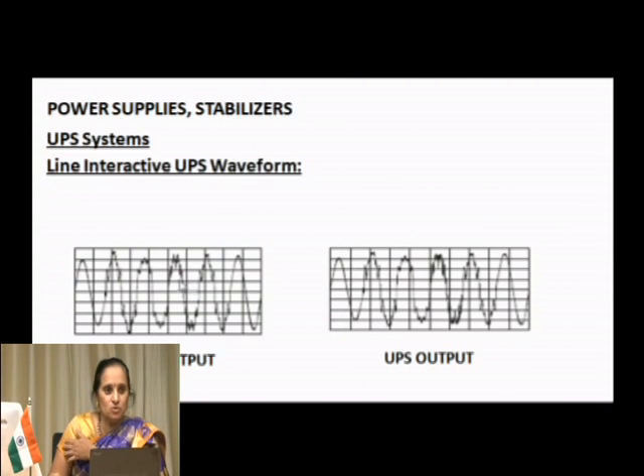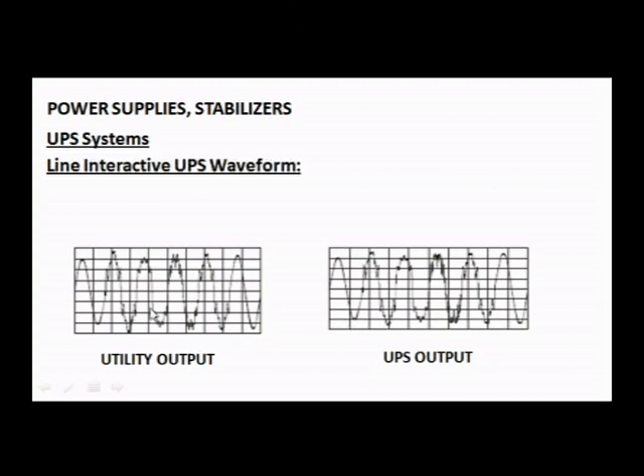I have shown one waveform for you to understand the utility output versus the UPS output. This is what the UPS output looks like - you can see it is not a pure sinusoidal waveform, there are some harmonics and noise signals available. This can be used in loads which are not bothered about the exact sinusoidal wave shape or precise waveforms.